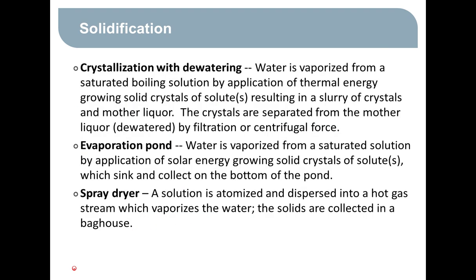The solidification step in a ZLD scheme is one of basically three ways you can do that. One is to use crystallization with dewatering, and that's what we're going to talk about in this particular presentation. But don't forget that when the conditions are suitable, evaporation ponds and spray dryers can also be used to achieve solidification. The kicker on those is that for an evaporation pond, obviously, you've got to be in an area with good solar energy and lots of empty land. As far as spray dryers are concerned, you need waste heat. So those conditions aren't always present.